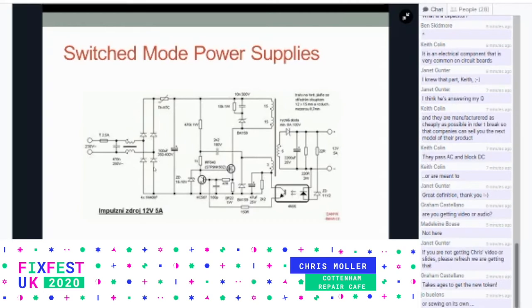These bridge rectifiers do sometimes fail, and they run quite hot. If one of these diodes fails, then the fuse will blow. This particular one has a negative temperature coefficient thermistor in there as well, to provide extra protection.